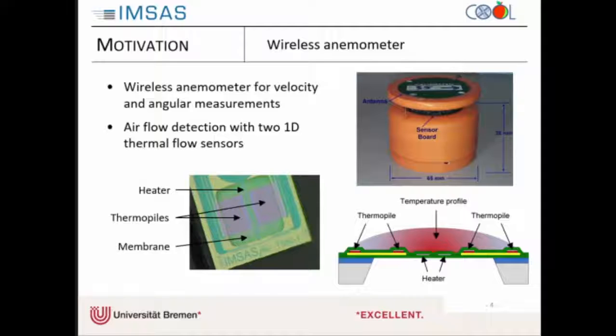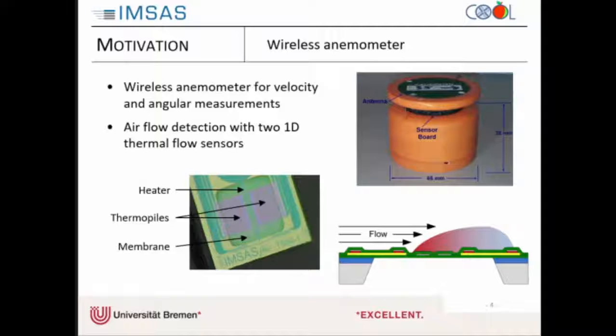On this sensor board, there are 2 one-dimensional flow sensors. The sensor is the same as described. We have a heater in the middle, we have 2 thermopiles beneath it, and all of them are placed on a thin membrane for thermal decoupling. The principle is also already known. We have the heater, it distributes the temperature. If there's no flow, both thermopiles will measure the same temperature, and there is no differential of the voltage. If there is a flow, it will shift the heat to one side, and one thermopile will be hotter than the other one, and so we have a differential voltage we can measure.